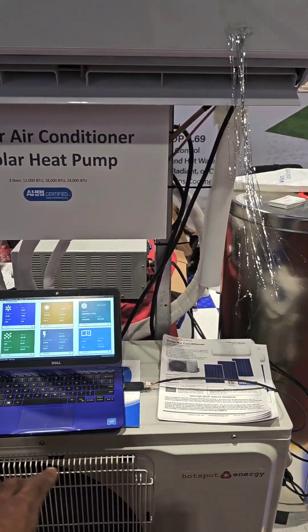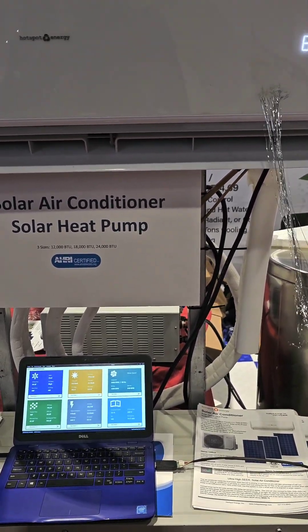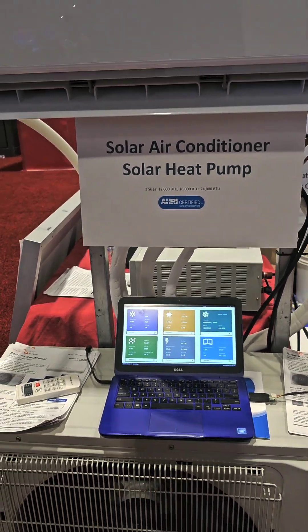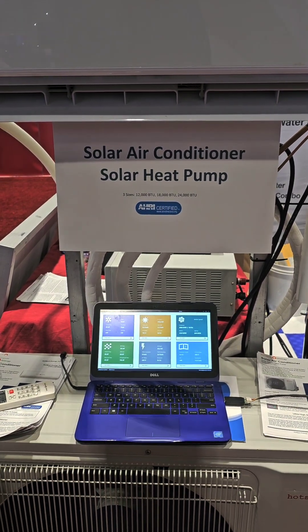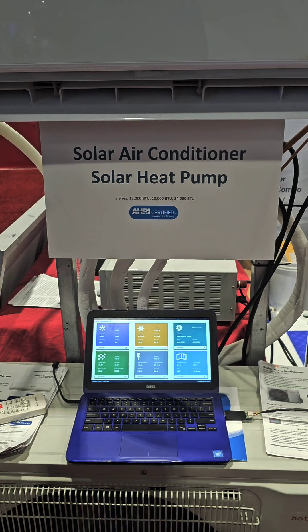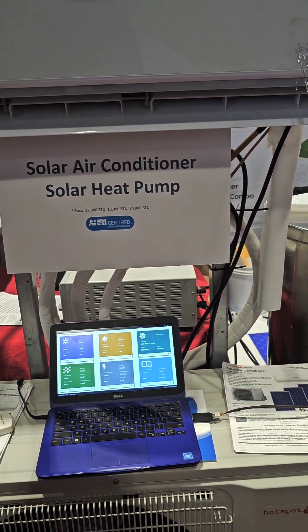My original question was, let's say your condensing unit — what if I want to hook this up to a Daikin head, would that work? It won't work with it. That's what somebody asked me on YouTube too. I don't think any manufacturer cross-connects like that. Maybe it could, but you've got communication wires. I know there are some companies — not talking about Daikin — that use the same factory and just rename them. That's possible. His exact question was, can a Mitsubishi and an LG work together? I'm not sure they come from the same factory. You probably can't do a Mitsubishi and a Daikin — just different communication protocols.